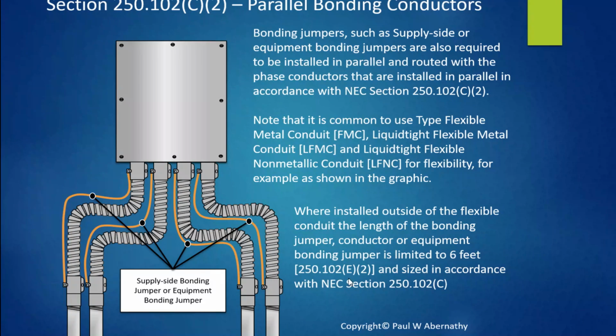But if you're also looking for use for equipment bonding jumpers, then you'll see that you also are going to limit it to 6 feet, and you would have to maintain. So here's the fitting, and here's the fitting. The conductors are running here, but you've got to maintain the integrity of this raceway to this enclosure.